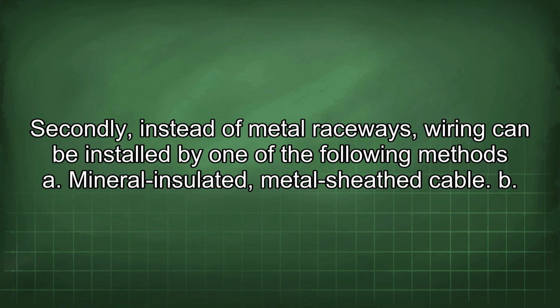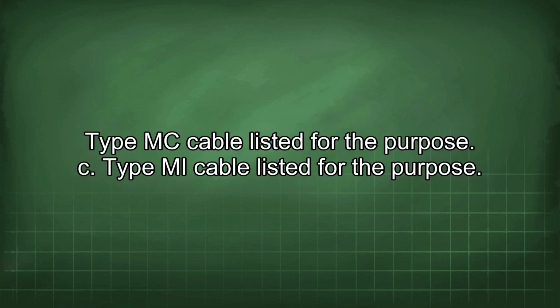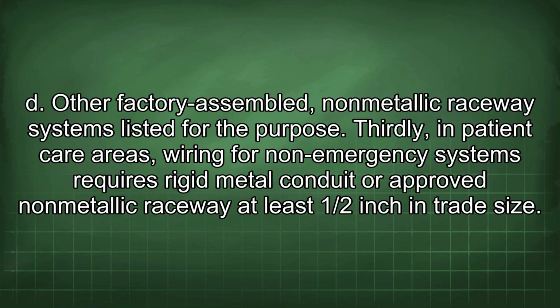A. Mineral insulated metal sheathed cable. B. Type MC cable listed for the purpose. C. Type MI cable listed for the purpose. D. Other factory assembled, non-metallic raceway systems listed for the purpose. Thirdly, in patient care areas, wiring for non-emergency systems requires rigid metal conduit or approved non-metallic raceway at least 1/2 inch in trade size.